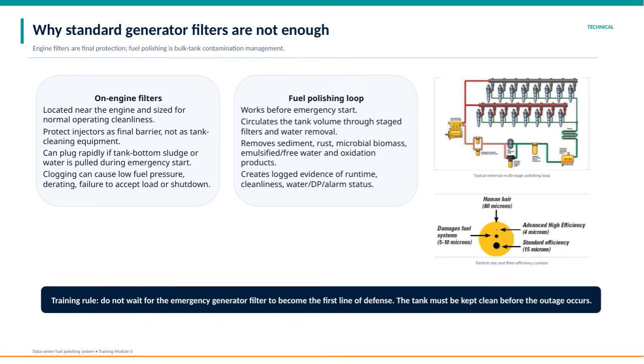In essence, the fuel polishing system serves as bulk tank contamination management, ensuring the fuel remains clean well before it reaches the engine filter. The key training takeaway here is not to wait for the emergency generator filter to become your first defense line. The tank itself must be maintained clean ahead of any outage to guarantee reliable generator performance.